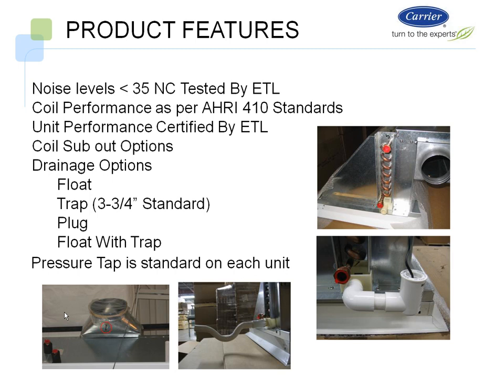Again, we talked about some of the noise levels of less than 35 NC, and that was tested by ETL. Again, the normal NC levels are anywhere between, let's say, 18 and 24. The less than 35 rating was up to about 1 to 1.2 inches of static, where you typically wouldn't be doing that, because if you had a beam and you needed 1 inch to 1.2 inches of static at it, I would probably tell you that's not the application for that beam. You might want to put something else there. So looking at where you're going to design a beam system is anywhere between 4/10 to 8/10 of an inch. Your sound levels are going to be somewhere in the realms of the 18 to 24 levels. So even quieter, even better than less than NC 35s.